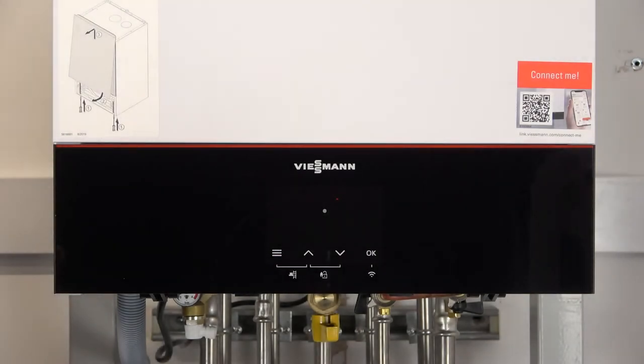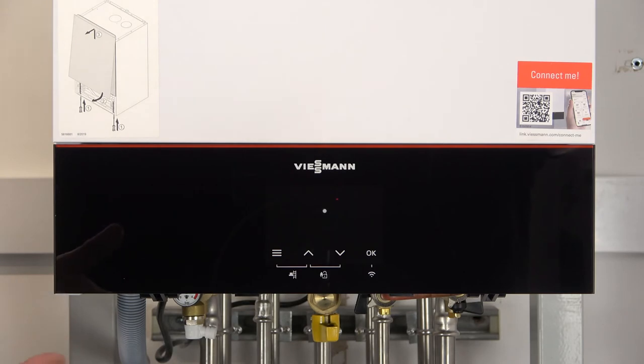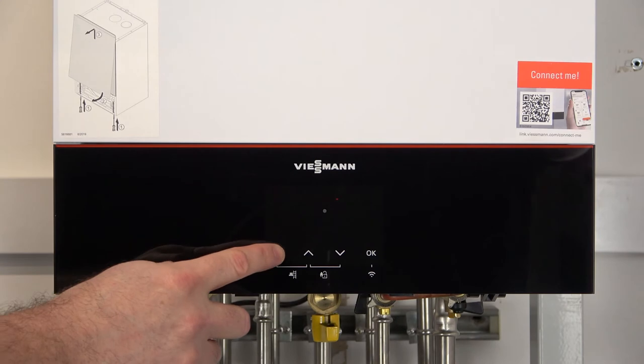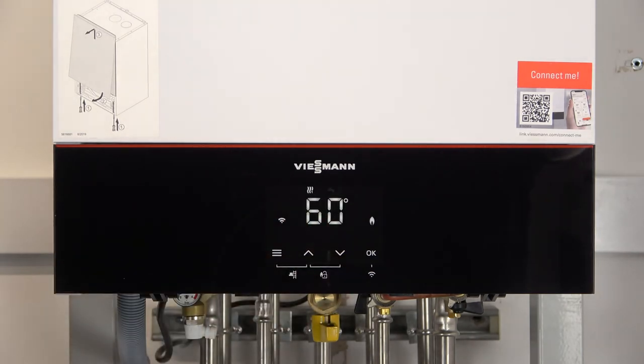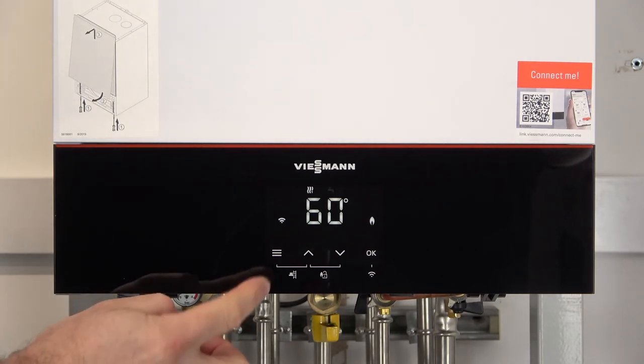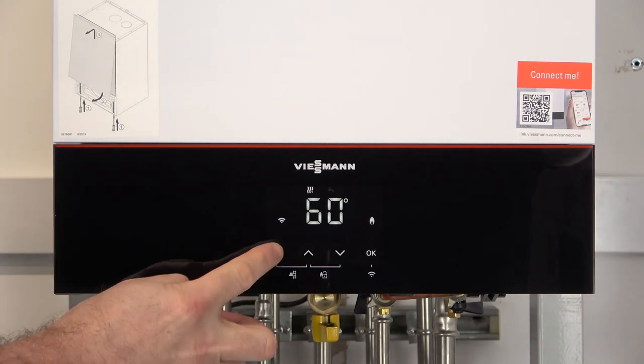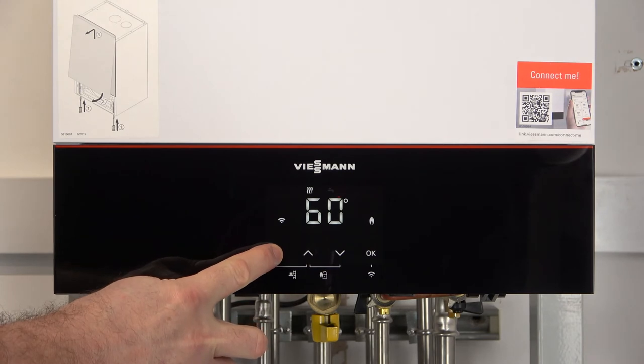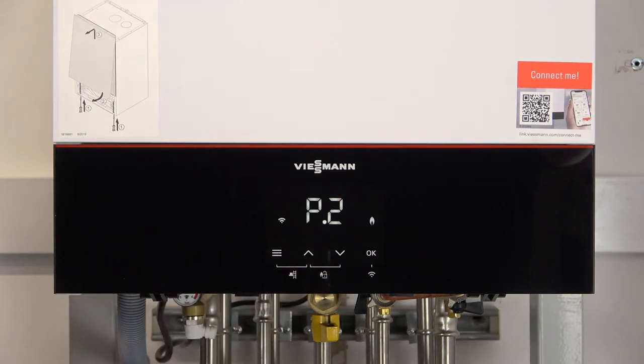When you get to the boiler, if the boiler has not been operated for quite some time and you've not interacted with it, you do get this light guide flashing on the front. To wake the boiler up, we just press the Menu button and you get the front display on the boiler. Now to access the P-Menu, all we do is simply hold the Menu button for a minimum of 4 seconds and the P-Menu appears.